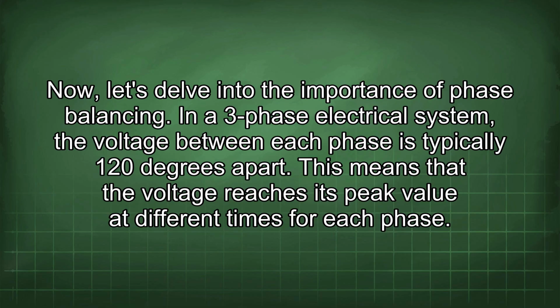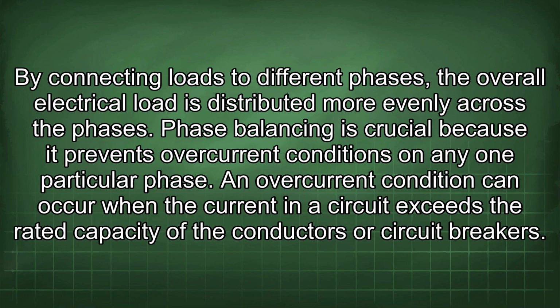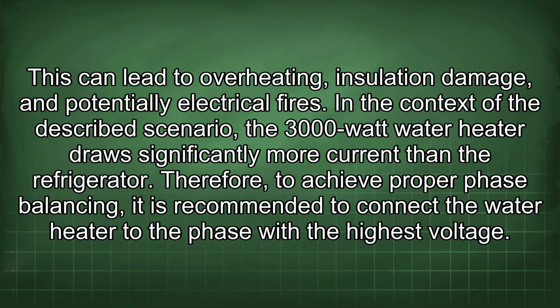In a three-phase electrical system, the voltage between each phase is typically 120 degrees apart. This means that the voltage reaches its peak value at different times for each phase. By connecting loads to different phases, the overall electrical load is distributed more evenly across the phases. Phase balancing is crucial because it prevents overcurrent conditions on any one particular phase. An overcurrent condition can occur when the current in a circuit exceeds the rated capacity of the conductors or circuit breakers. This can lead to overheating, insulation damage, and potentially electrical fires.